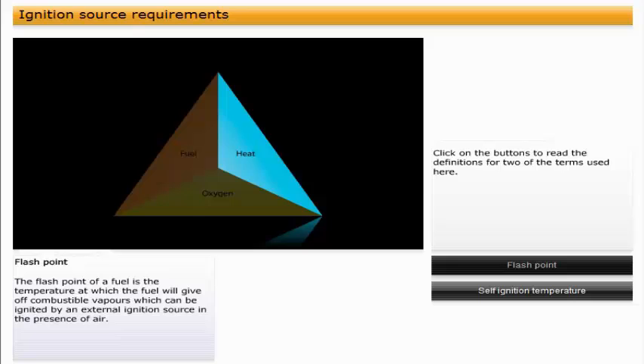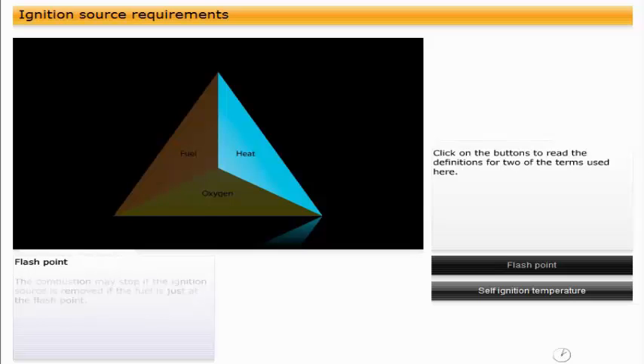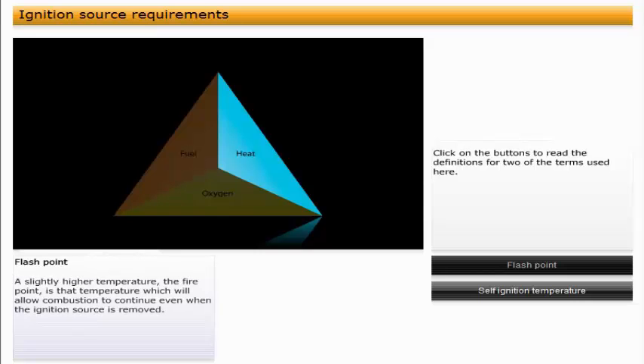The flash point of a fuel is the temperature at which the fuel will give off combustible vapors, which can be ignited by an external ignition source in the presence of air. The combustion may stop if the ignition source is removed if the fuel is just at the flash point. A slightly higher temperature, the fire point, is that temperature which will allow combustion to continue even when the ignition source is removed.